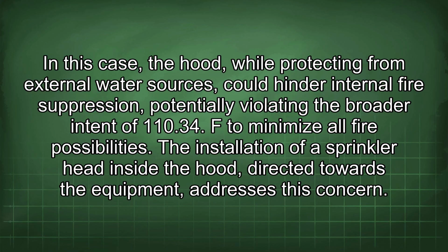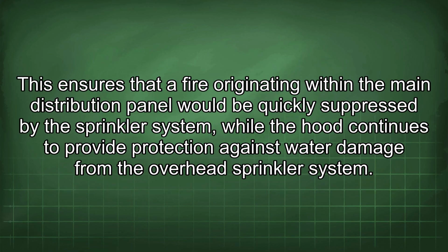The installation of a sprinkler head inside the hood, directed towards the equipment, addresses this concern. This ensures that a fire originating within the main distribution panel would be quickly suppressed by the sprinkler system, while the hood continues to provide protection against water damage from the overhead sprinkler system.